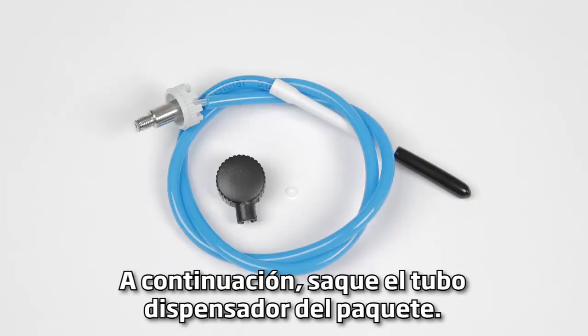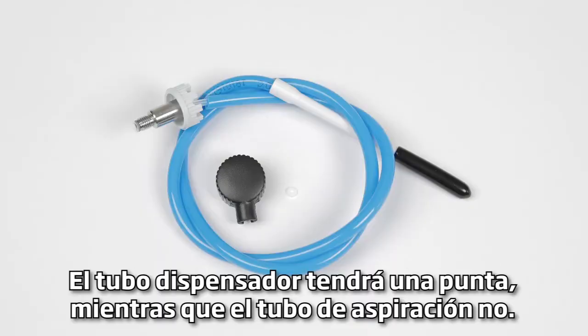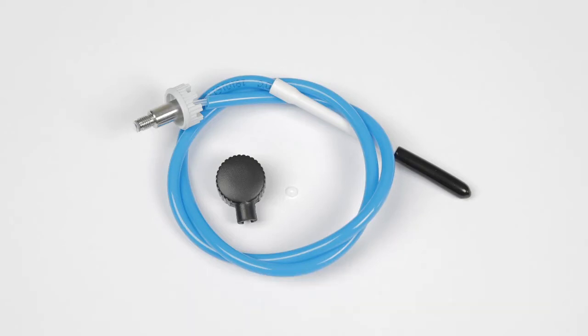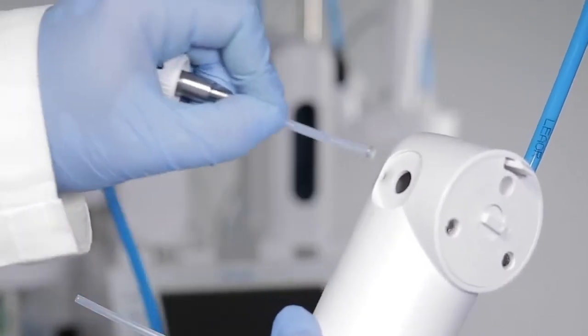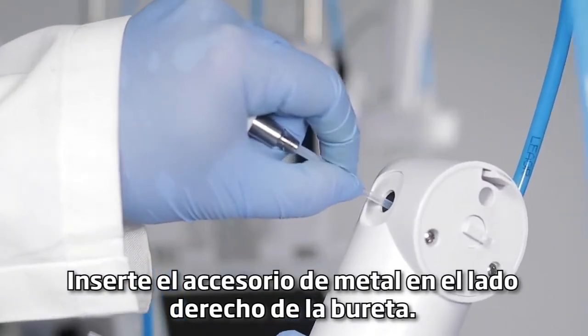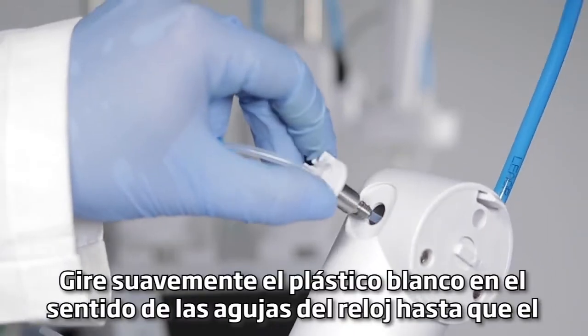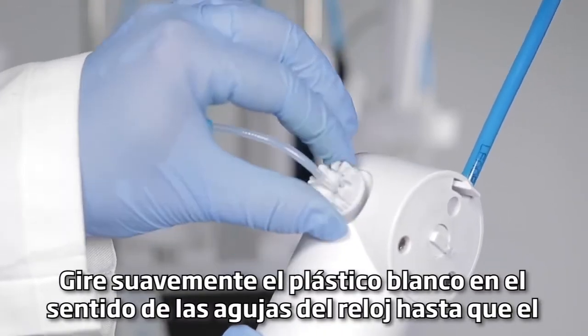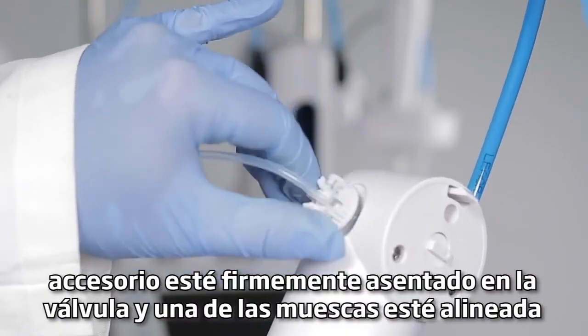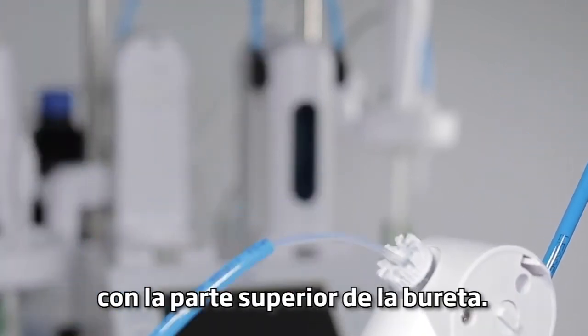Next, take the dispensing tube out of the package. The dispensing tube will have a tip on it, whereas the aspiration tube will not. Insert the metal fitting into the right side of the buret. Gently turn the white plastic clockwise until the fitting is firmly seated into the valve and one of the notches is aligned to the top of the buret.